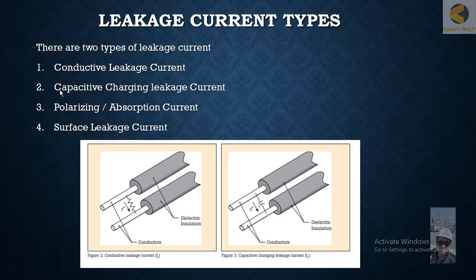This capacitive charging leakage current is called capacitive charging leakage current. After a certain time, this current will decay. Initially the resistance reading will be lower, but as the charging current decays to almost zero, the reading will increase and become stable.